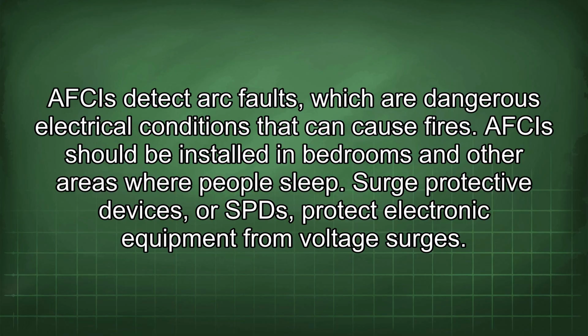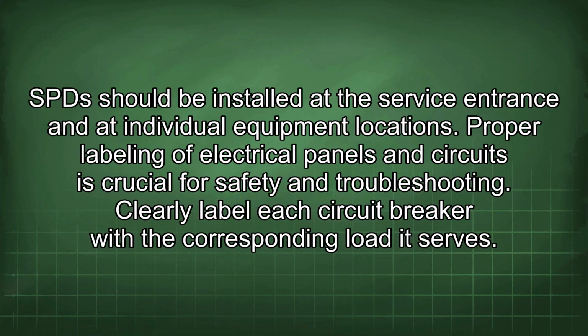Surge protective devices, or SPDs, protect electronic equipment from voltage surges. SPDs should be installed at the service entrance and at individual equipment locations. Proper labeling of electrical panels and circuits is crucial for safety and troubleshooting. Clearly label each circuit breaker with the corresponding load it serves.